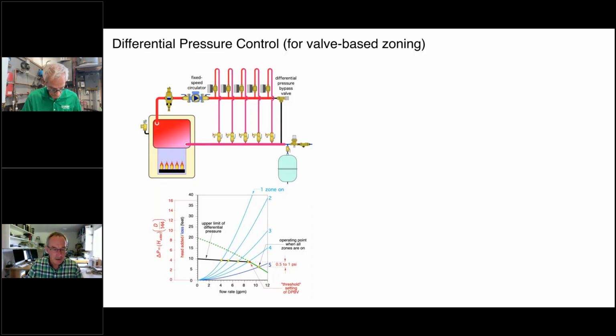If we look at it on a graph, instead of the operating point moving all the way up the pump curve as the zones close, it's going to come up to what's called the threshold setting of the differential pressure valve. It is as if the upper portion of that pump curve gets truncated to this black line. Our pressure goes up from this point to this point, but once that differential pressure valve is active, we have very little increase in differential pressure. So that was a way to approximate what I'll call constant differential pressure control.